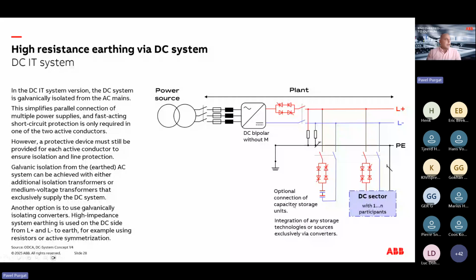And we can continue. So the second option is using IT systems, so essentially high impedance or ungrounded systems. These systems are the most popular, normally are deployed also with insulation monitoring. You can see that one of the key things is that now we have the semiconductor device only in one of the polarities. And here it's important to distinguish because we have the electromechanical device that provides the galvanic isolation, but we have semiconductor device that provides the short circuit current interruption function.